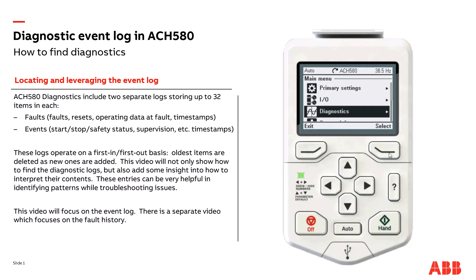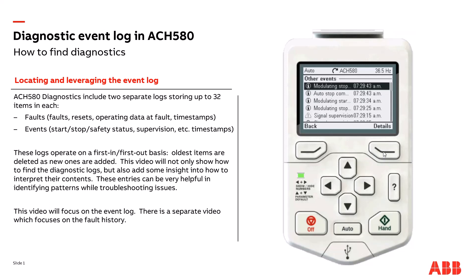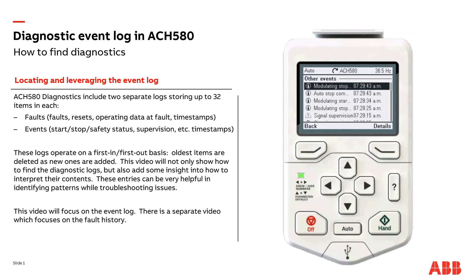One additional item I neglected to cover is what is actually in the event log on a particular entry. Let's go back into the event log, select one of the events, and navigate a bit deeper. Here are the details: the textual description, the corresponding hex code, and what's called the aux code — some faults and events have multiple underlying triggers captured there. We also see the specific date and time when the event occurred, and the drive on-time. That's the details contained in the event log.